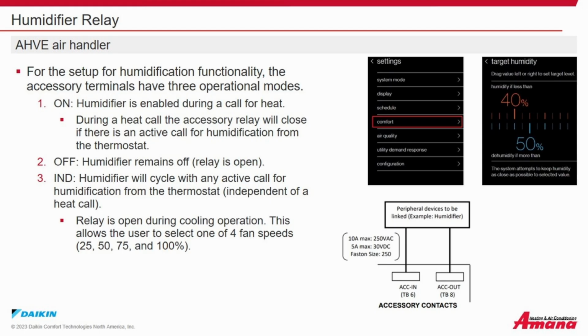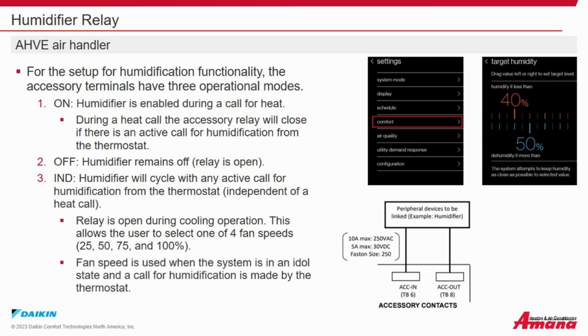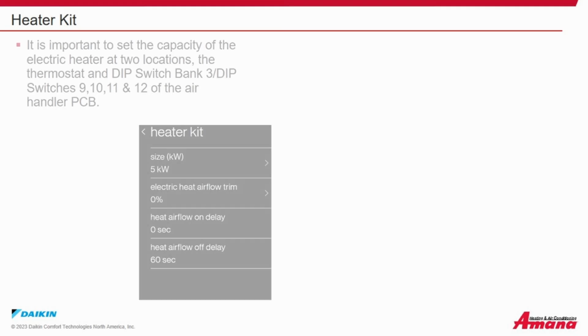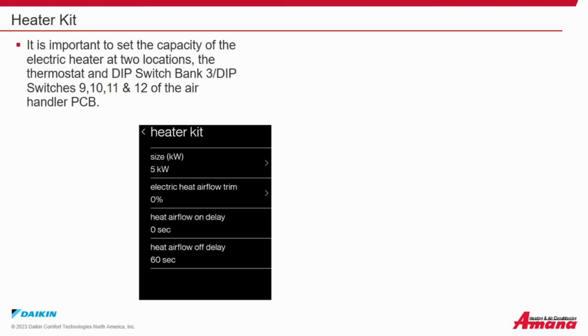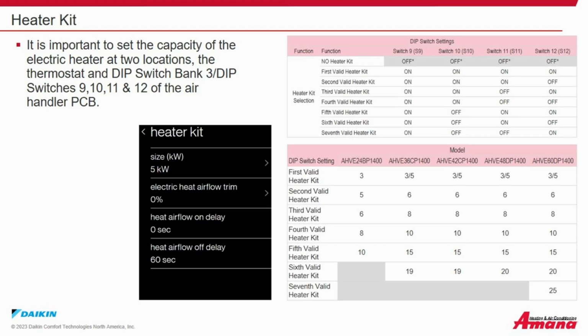This allows the user to select one of 4 fan speeds, 25, 50, 75, and 100%. The fan speed is used when the system is in an idle state and a call for humidification is made by the thermostat. Heater kit. It is important to set the capacity of the electric heater at two locations: the thermostat and the dip switch bank 3, dip switches 9, 10, 11, and 12 of the air handler printed circuit board.